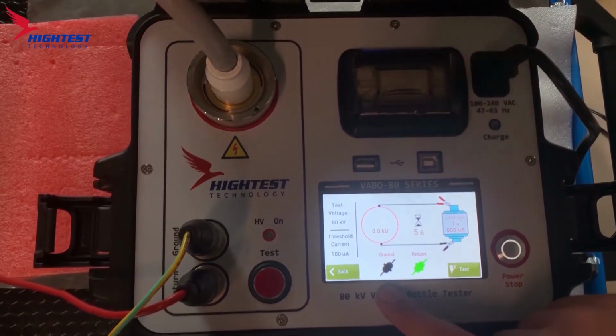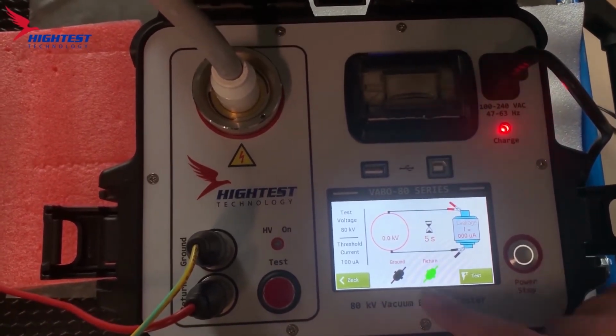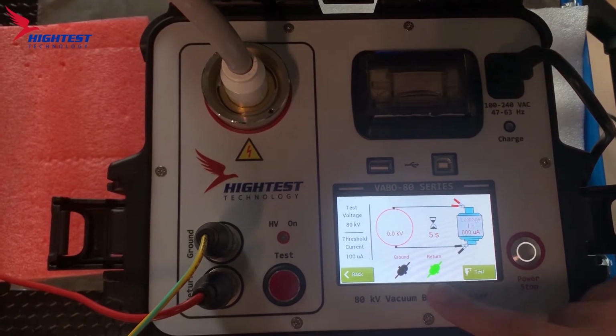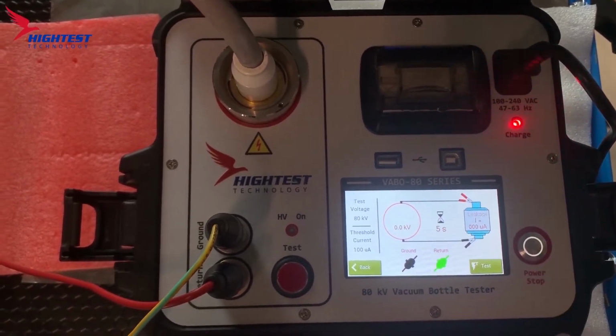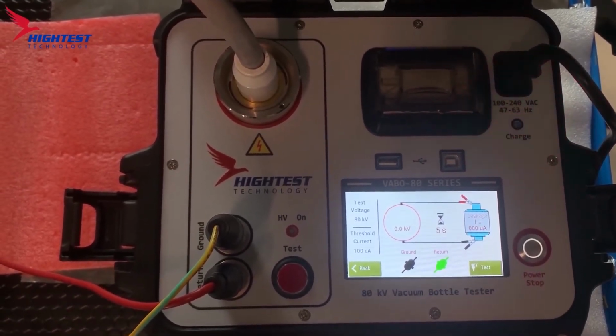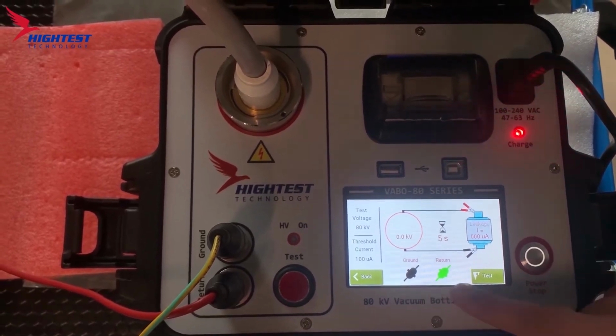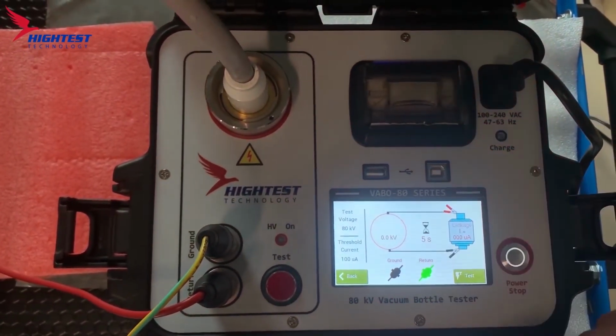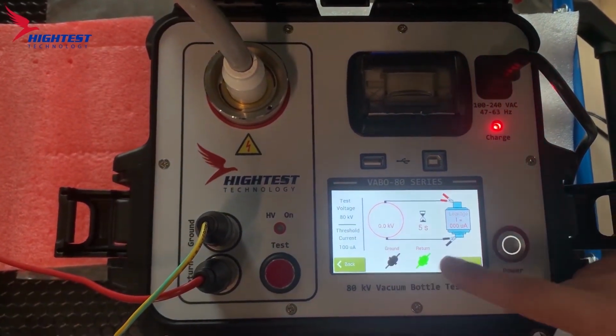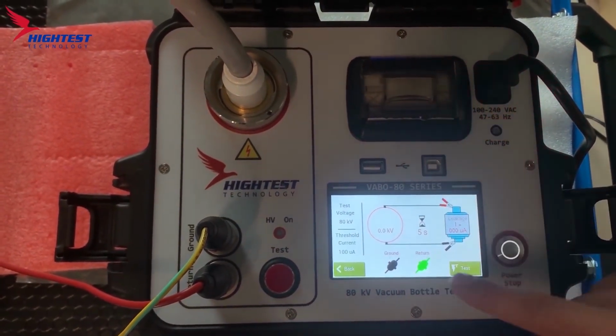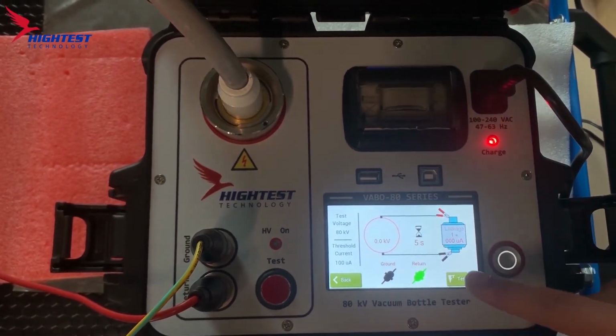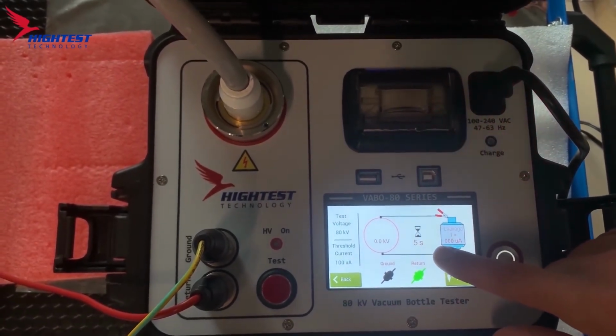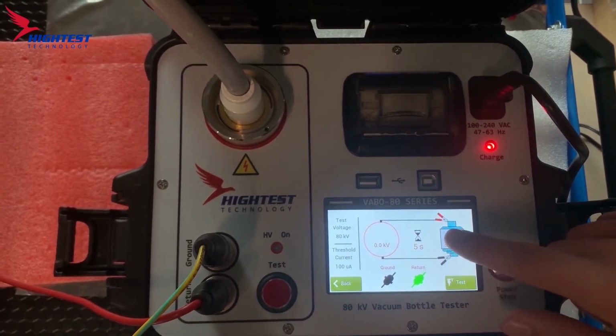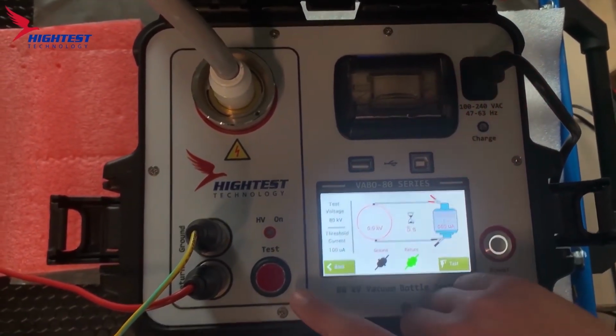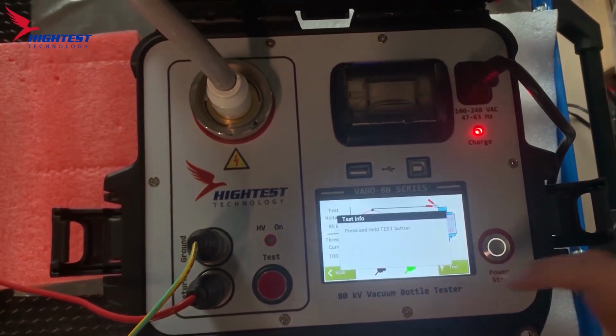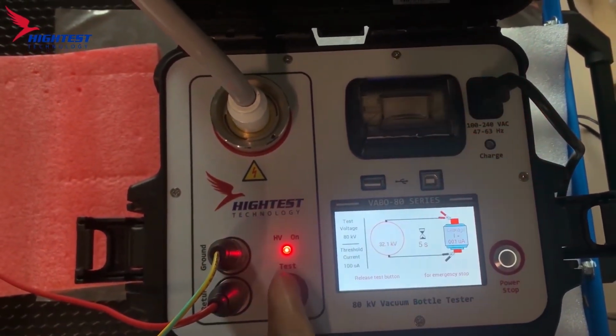And here you can see the ground and the return are highlighted. This indicates that the ground and the return are both attached and are properly connected to the device. If they are not, they show that they are disconnected here. Here you can see the test voltage and threshold current, and you can see all of the options for the device here that indicates the test. And here you can see the indication for the time. We indicated 5 seconds, so that will be the duration of the test and how long you will hold down the button. Please select test.